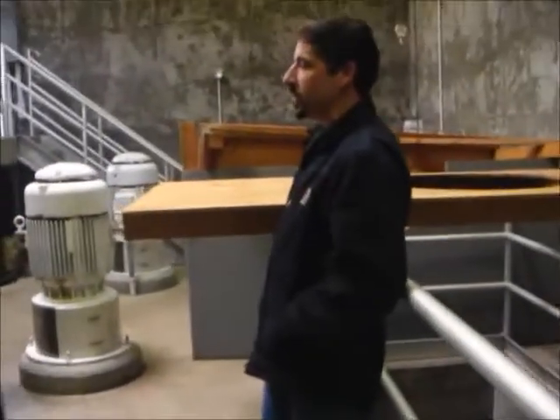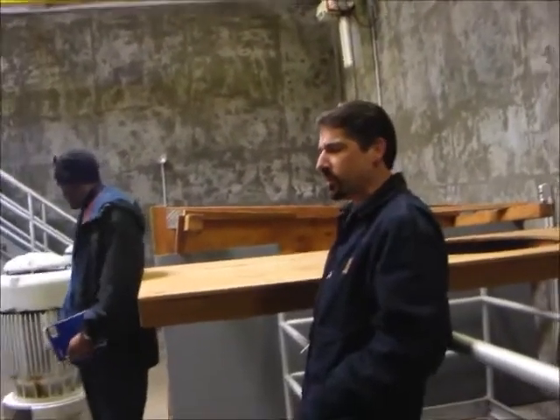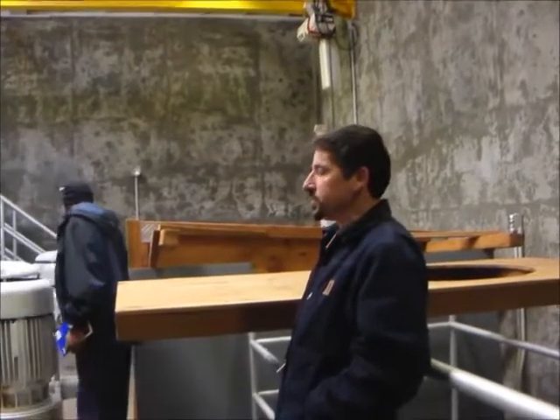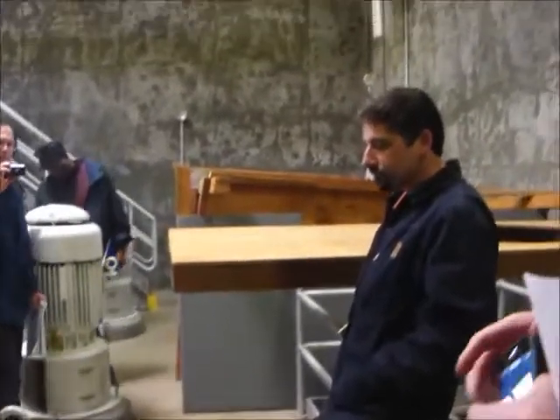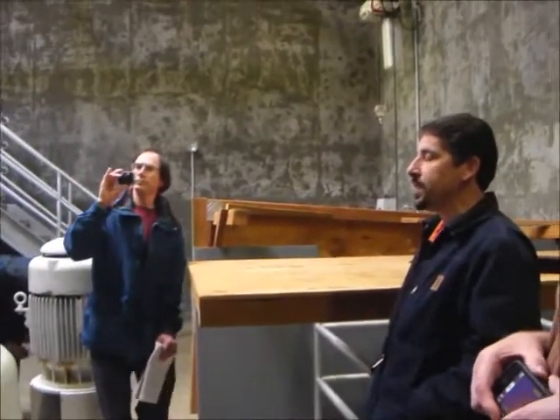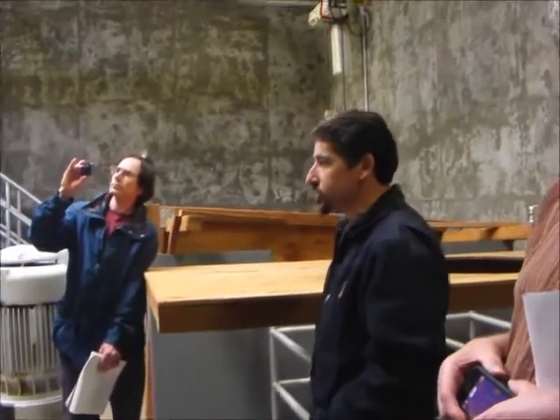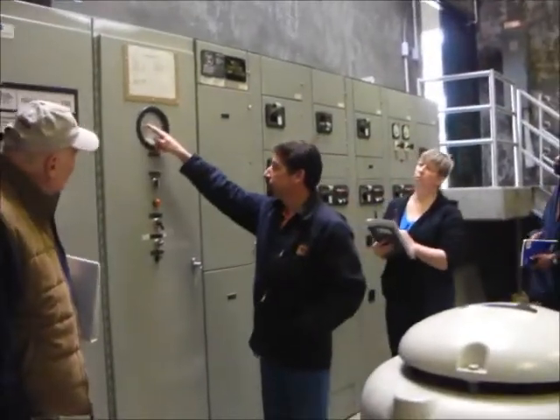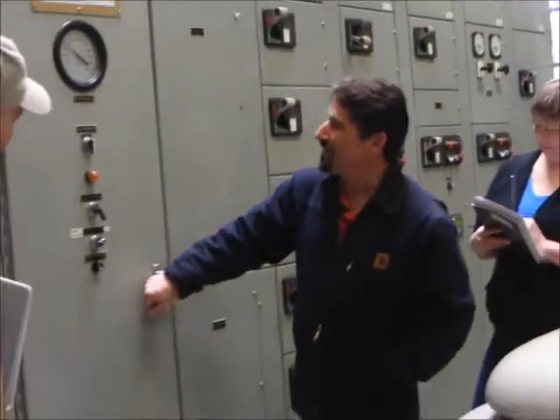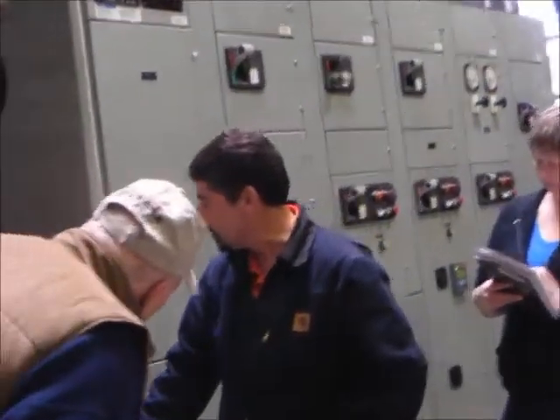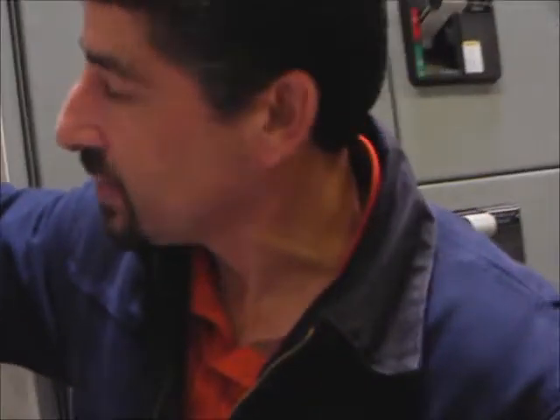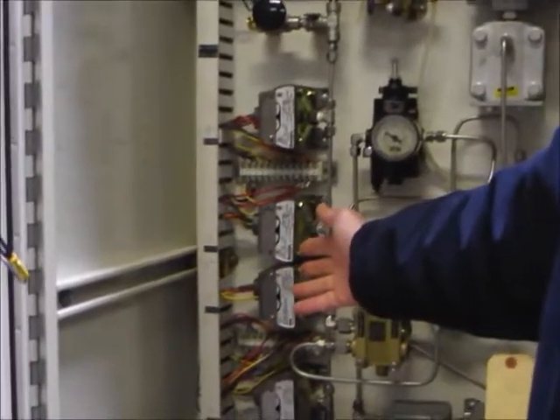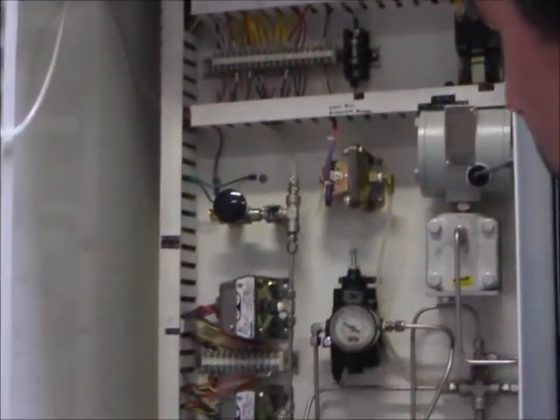The station has 3 pumps. I believe they're 40 horsepower Marathon pumps. I think I gave you all the breakdown on them. Pumps are controlled the same as the other station with a bubbler system, a pressure system, which tells you the level of the wet well. This is maintained with the air compressor system. This is the one that gives the 4-20 milliamp signal that tells these pressure switches what the level is in the wet well. That's basically the same. It has a backup float system to go with the pressure system.